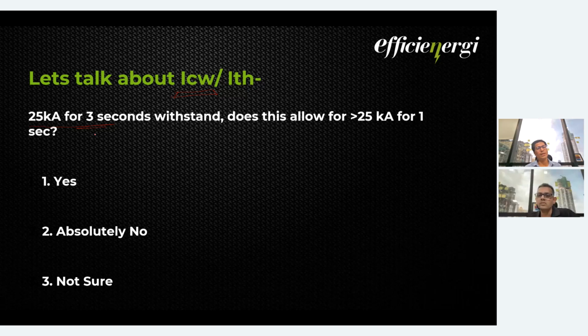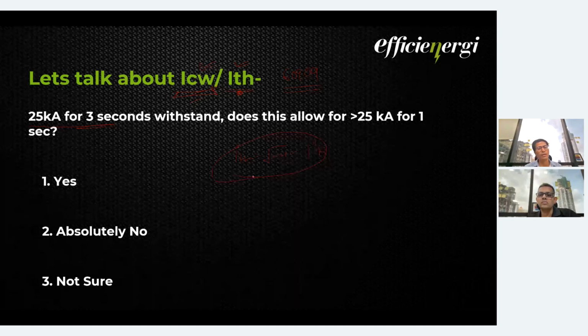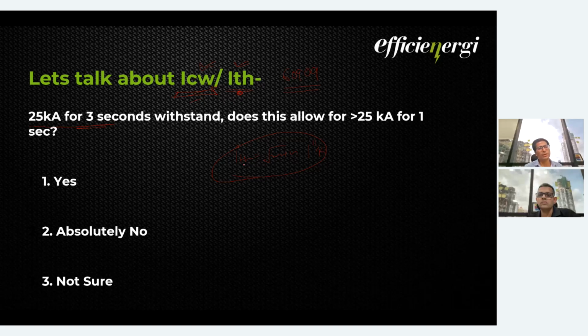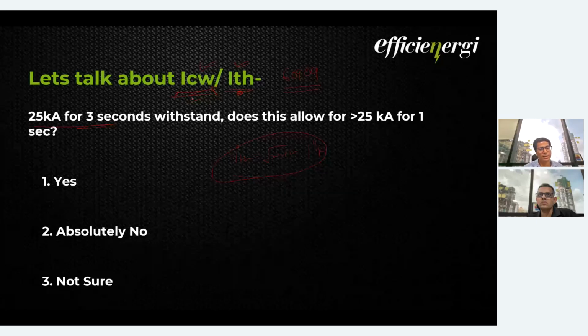ITH is quite different from ICW, but in ETAP you can see people showing you the ITH value to compare with the ICW. The ITH value that we see in 60909 is different, and the ICW value is different. In IEC 60909, the ITH value is nothing but some factors m and n and I double dash k. So this is basically the thermal capacity, whereas the ICW takes care of the thermal stresses as well as the mechanical stresses. So there is a difference, but in ETAP, you can see these values are given in this relation only.